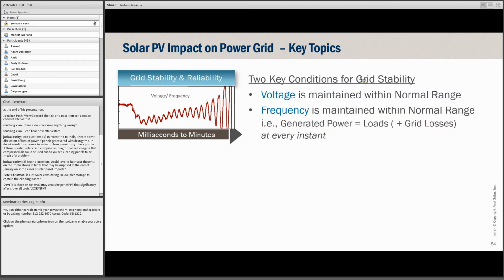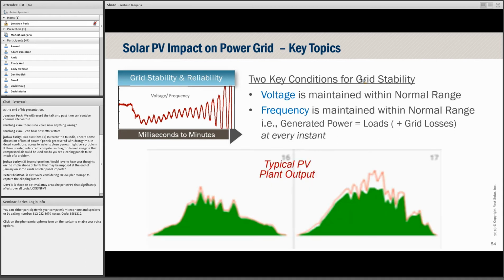I'm not going to go into a lot of those details, but the focus will be on the first category - maintaining voltage in the normal range and frequency, which is a proxy for ensuring generator power equals the loads plus any losses at every instance. How do we manage that, especially given a typical PV plant output, which can vary as shown here, where the red line is the irradiance and the green line is the power output of the plant?